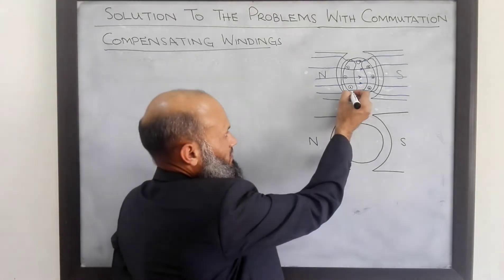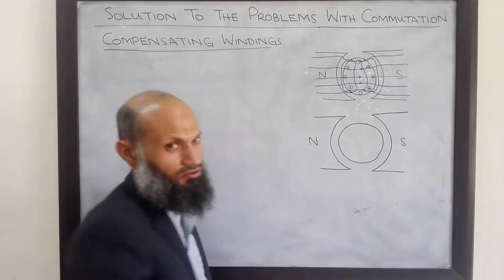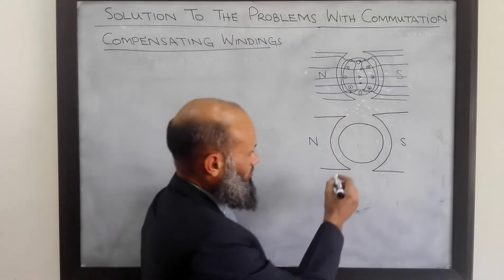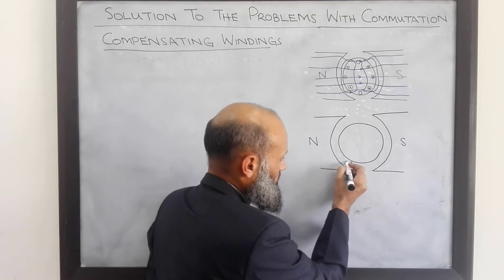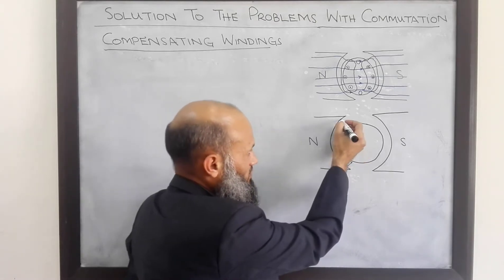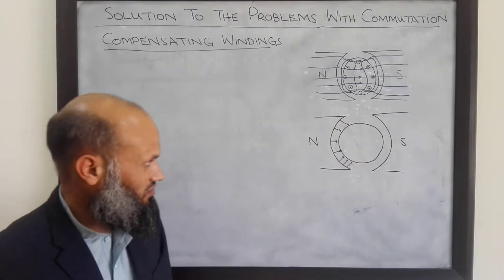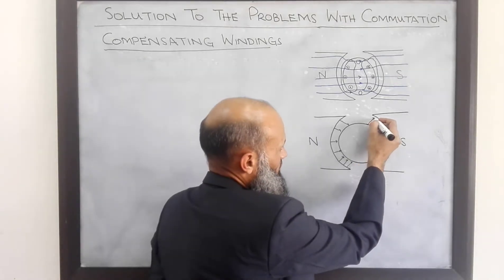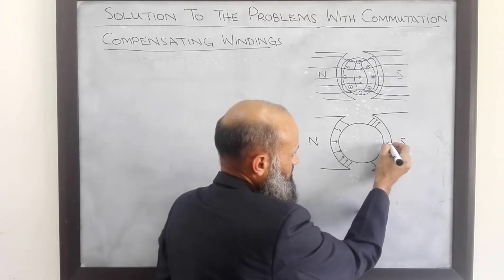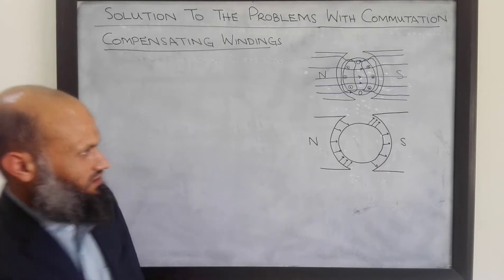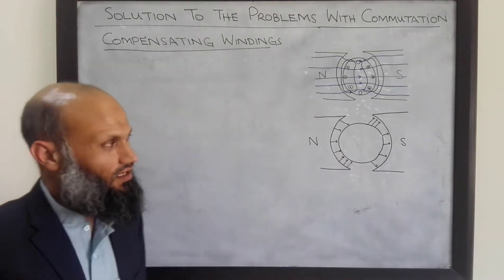At one end of the pole, the MMF due to main poles and the MMF due to the rotor windings are in the same direction; therefore MMF and flux density will increase at that end. At the other end, flux density will decrease because the two MMFs are in opposite directions. Likewise for the other pole, flux will increase on one side and decrease on the other. So flux distribution along the surface of the rotor is no longer uniform. This effect is called armature reaction.